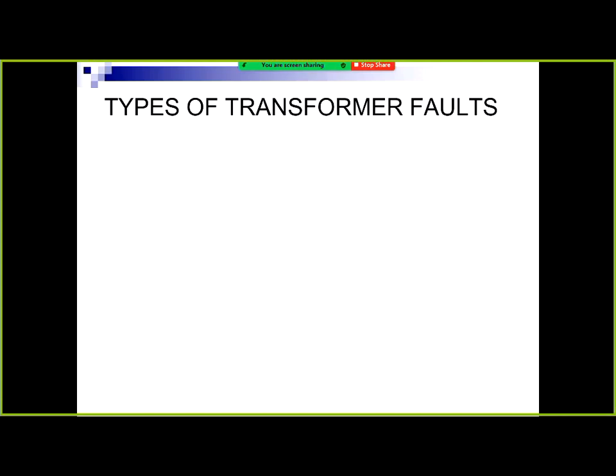In the last year we had a transformer that failed up at Cumberella Park, which is sort of on the Darling Downs out there. It was a 300 MVA transformer, but I don't know the reasoning why it failed. It had a bushing fault and threw out porcelain around the area a bit. When we build these transformers, they've got a blast wall between transformers. So if you have a fault on one transformer, you don't throw porcelain into the next transformer and damage both your transformers that are there.